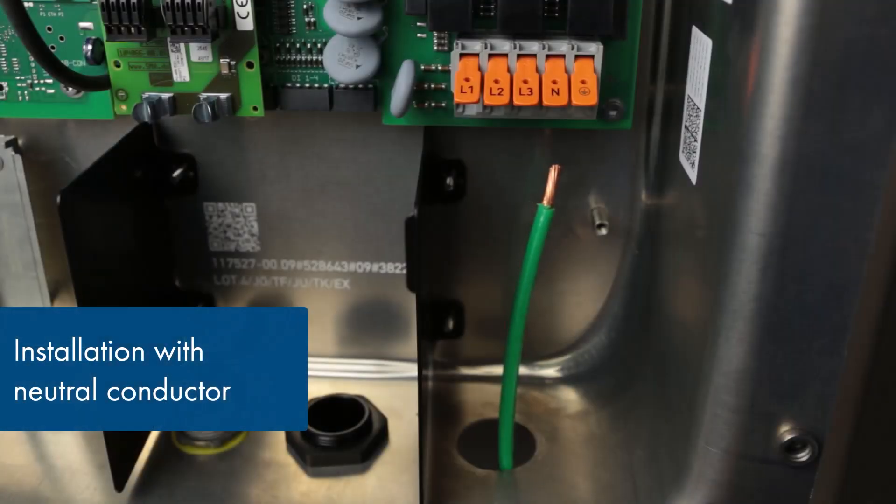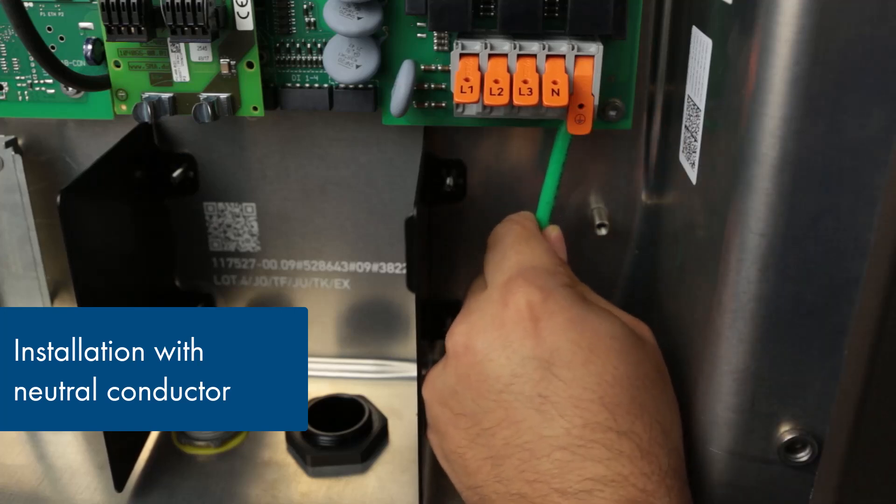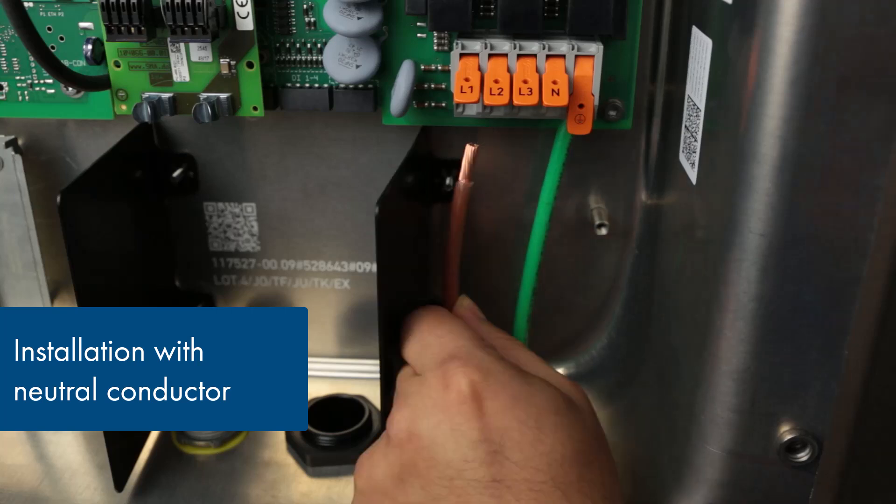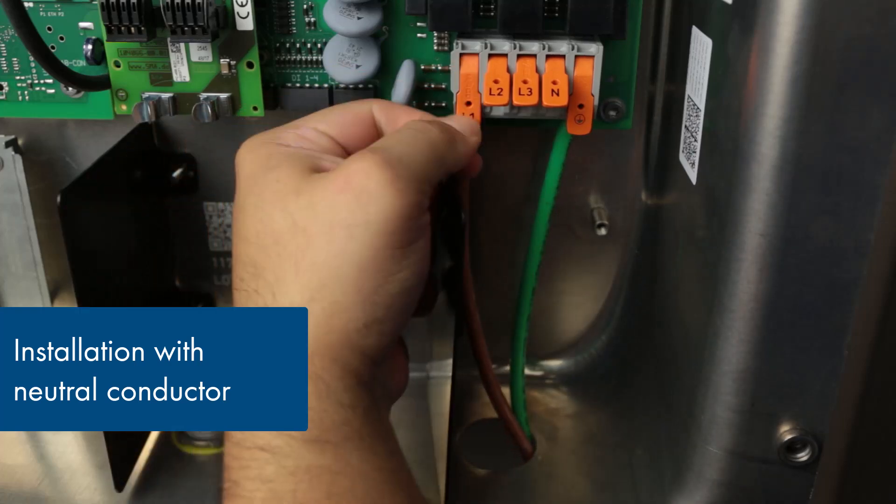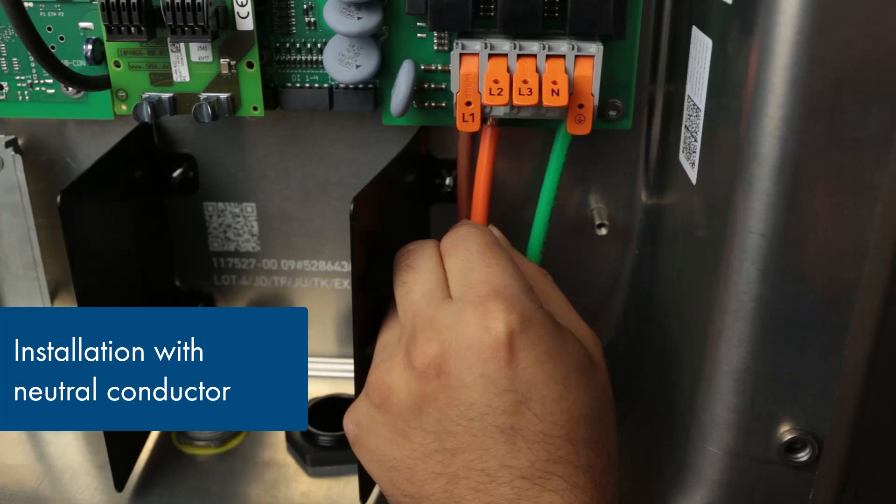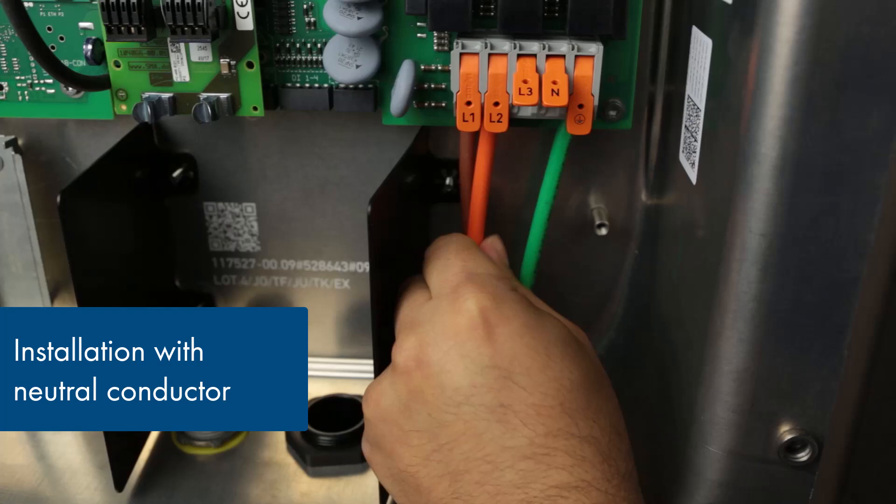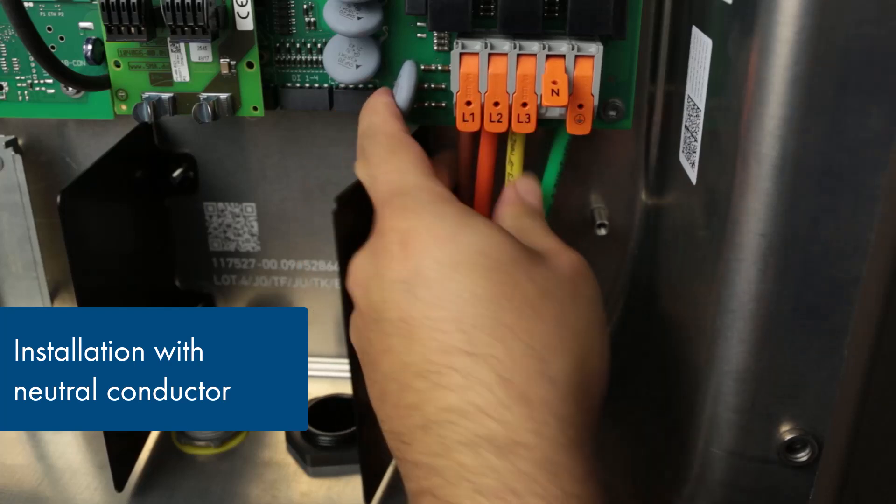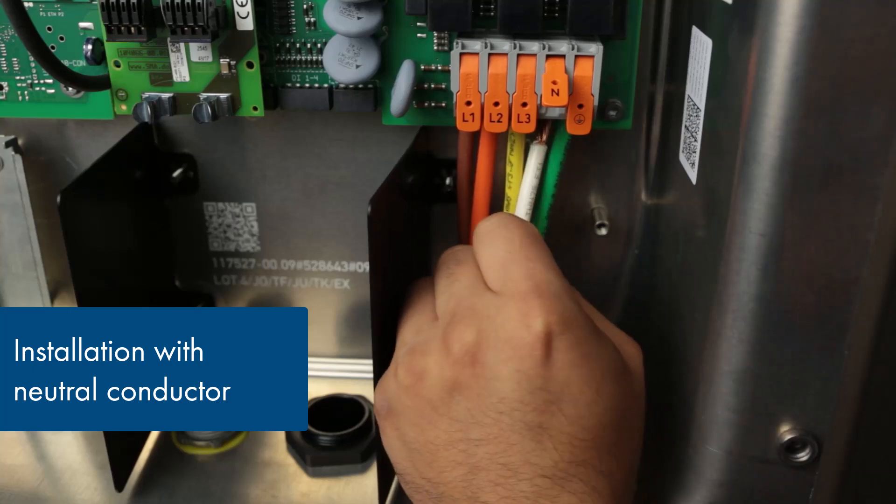To connect the AC conductors, strip back 3 fourths of an inch of the insulation of the wires AWG6 or AWG8 and insert the ground conductor into the terminal with the ground symbol and securely close the lever. Proceed to insert the L1, L2 and L3 conductors into the respective terminals, ensuring a secure seating for each. Then insert the neutral conductor into the appropriate terminal.